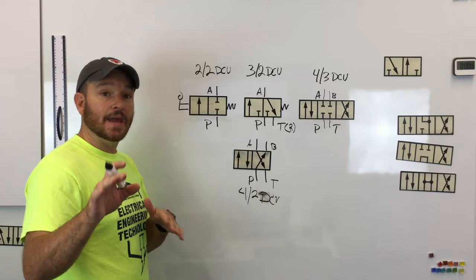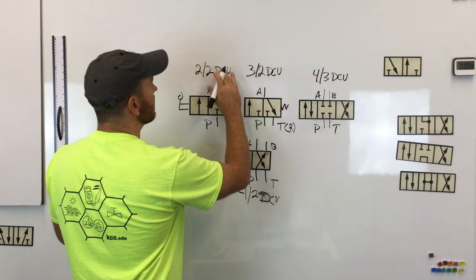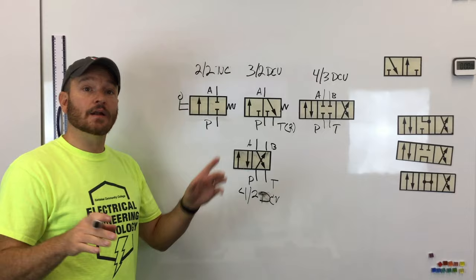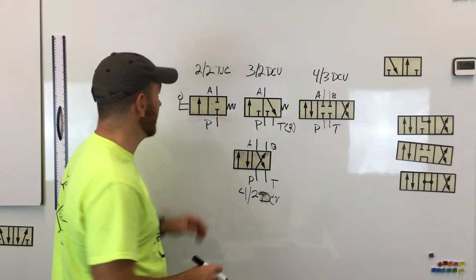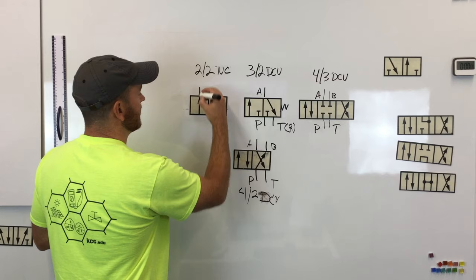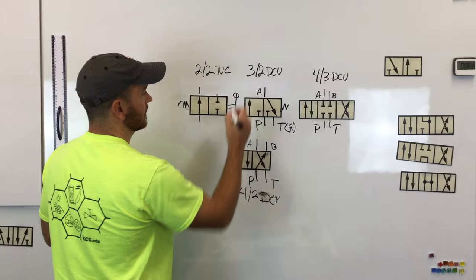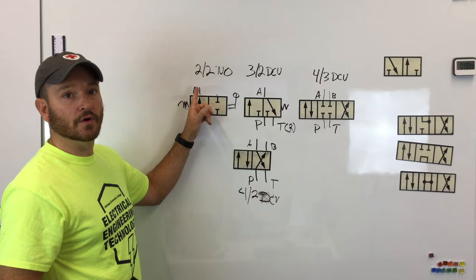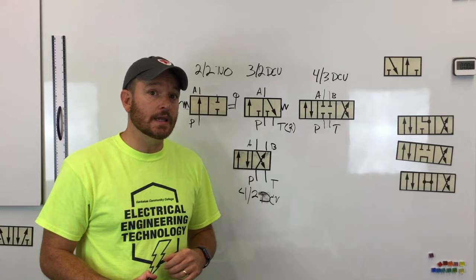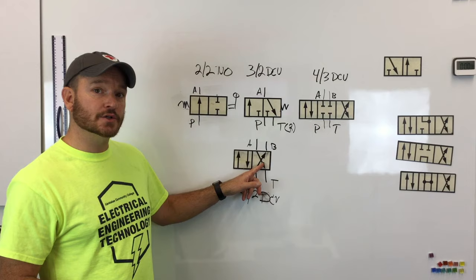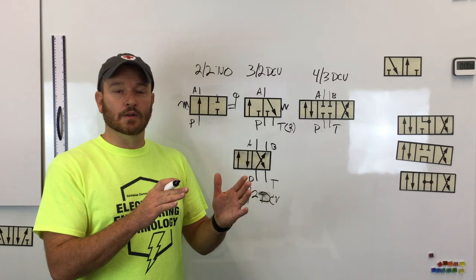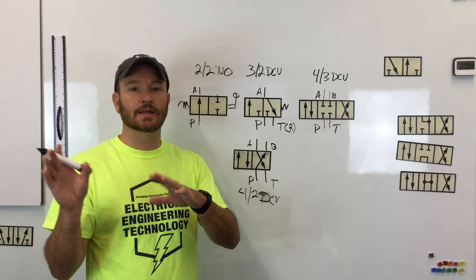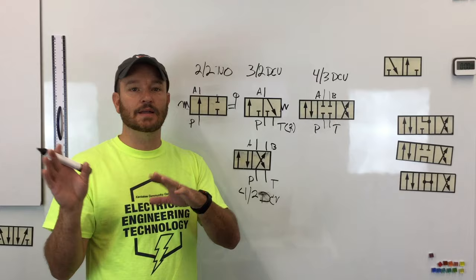Some manufacturers identify this as a two-two normally closed directional control valve. You can also make it normally open — in its normal position, oil will flow right through. However, the concept of normally open or normally closed gets tricky on a four-two directional control valve, because there isn't really a normally open or normally closed position. Some say it indicates whether the cylinder is extended or retracted, but that doesn't make sense because you can switch that by swapping your A and B ports.